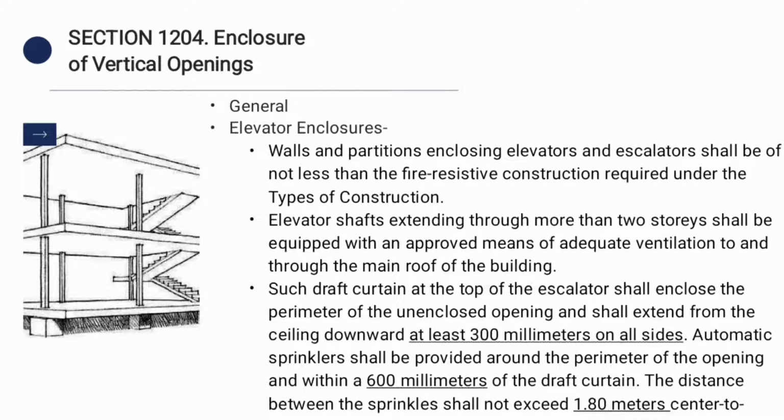So, diri underline na nako para mas maklaro dito siya. And then, the automatic sprinklers shall be provided around the perimeter of the opening and within 600 millimeters of the draft curtain. And then, ang distance sa imuhang sprinklers, it should not exceed 1.80 meters center to center.